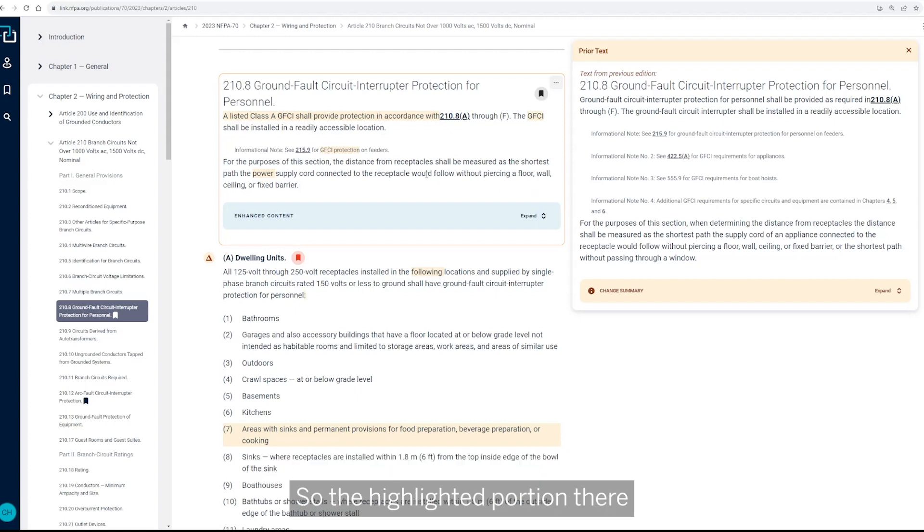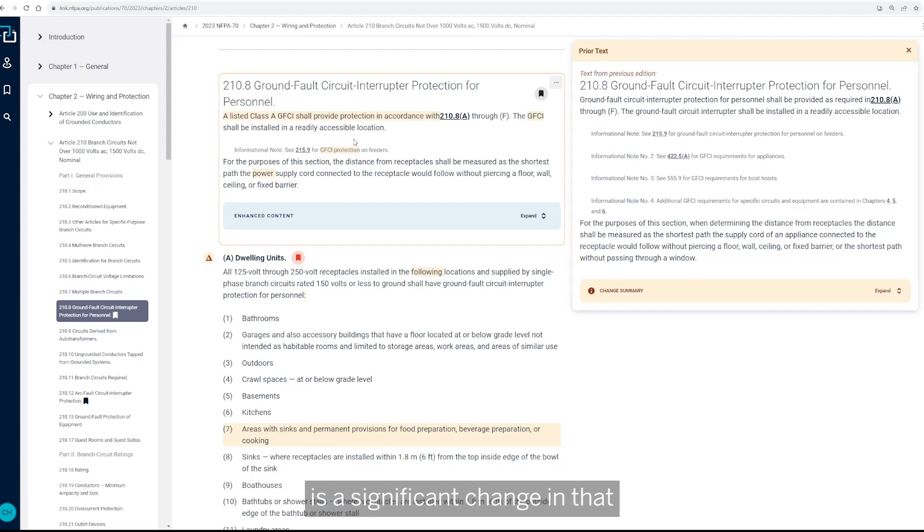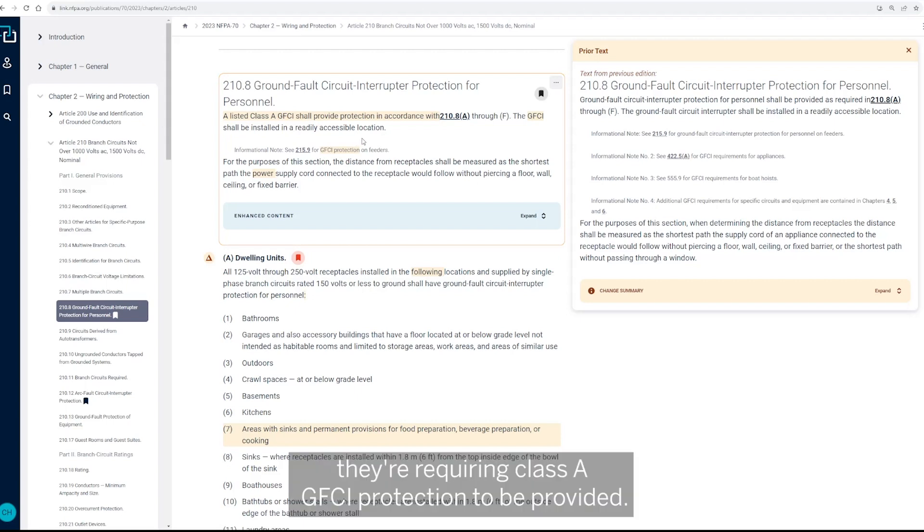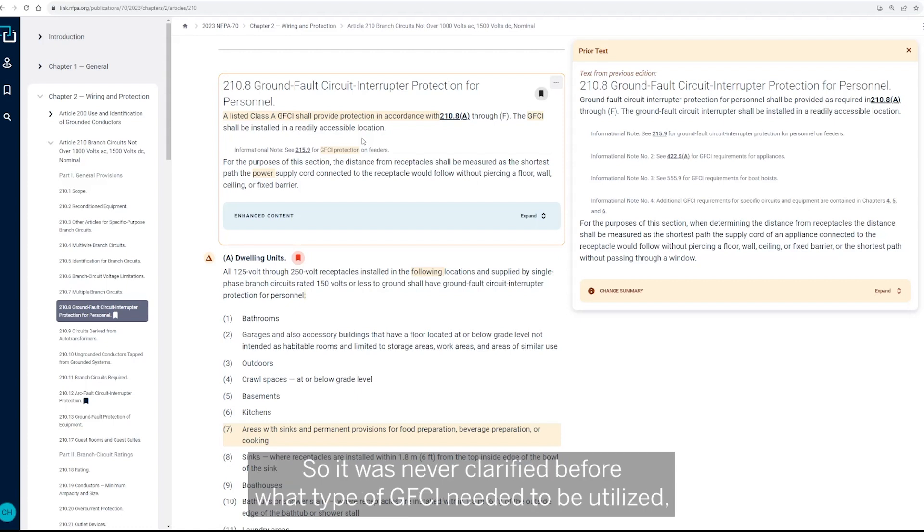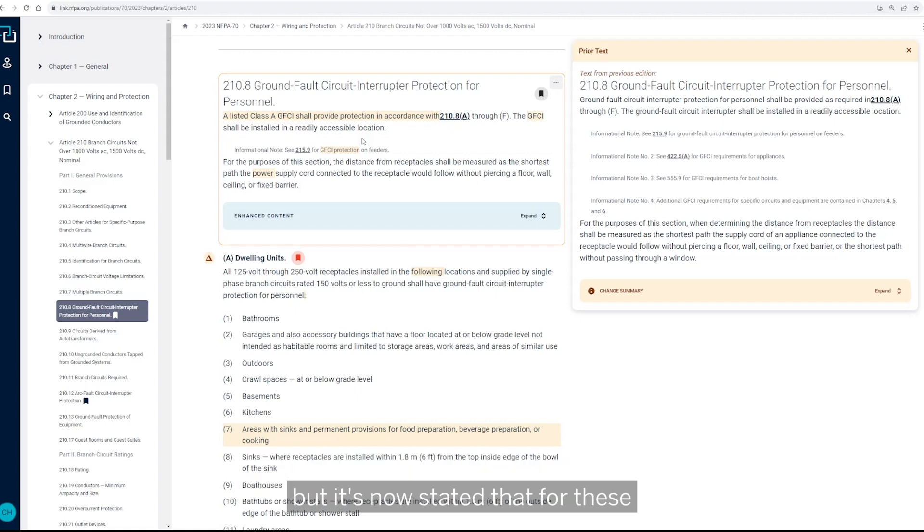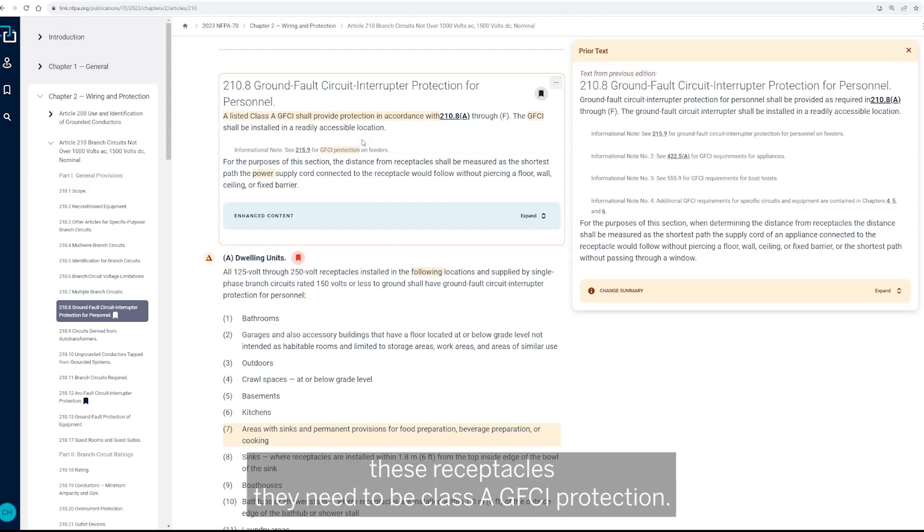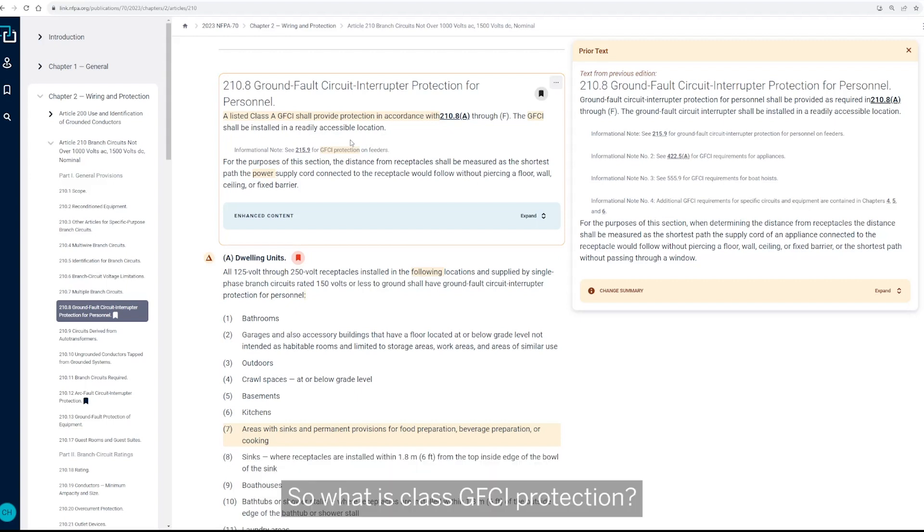So the highlighted portion there is a significant change in that they're requiring Class A GFCI protection to be provided. So it was never clarified before what type of GFCI needed to be utilized, but it's now stated that for these receptacles they need to be Class A GFCI protection.